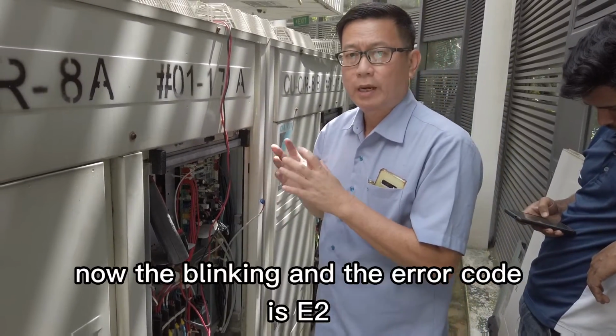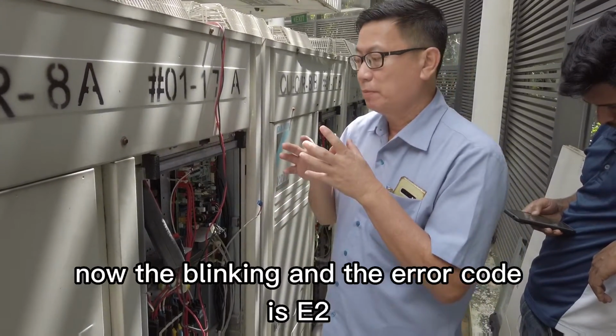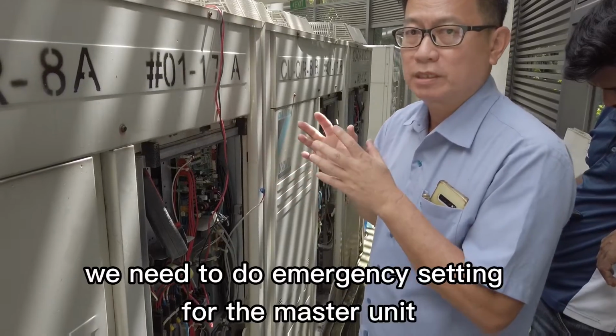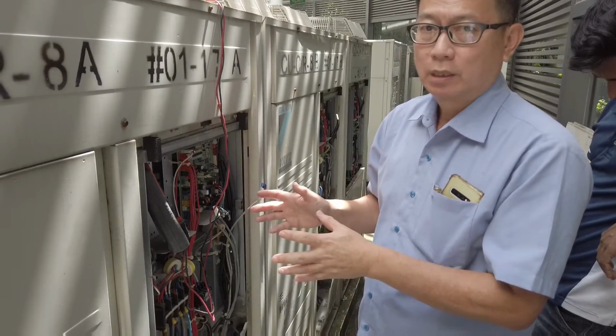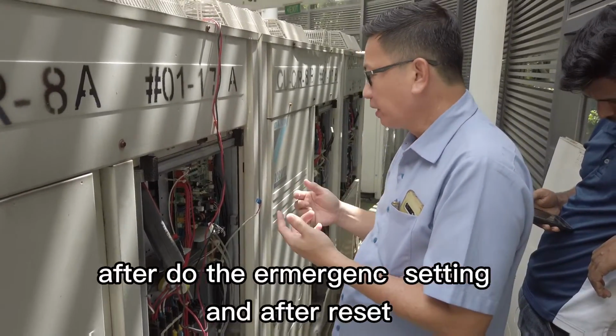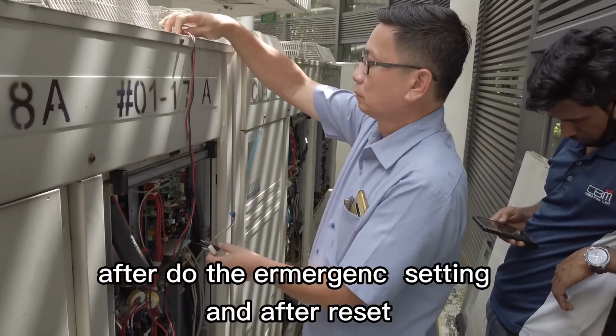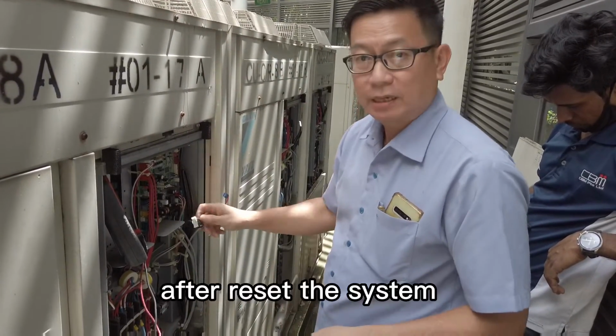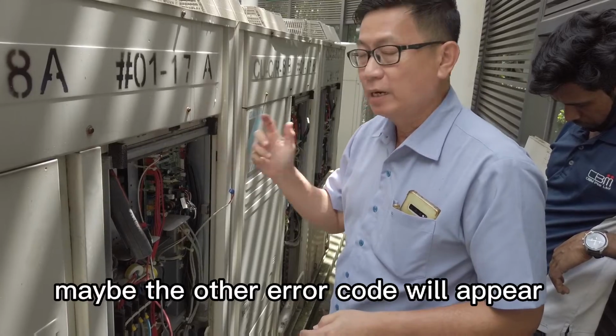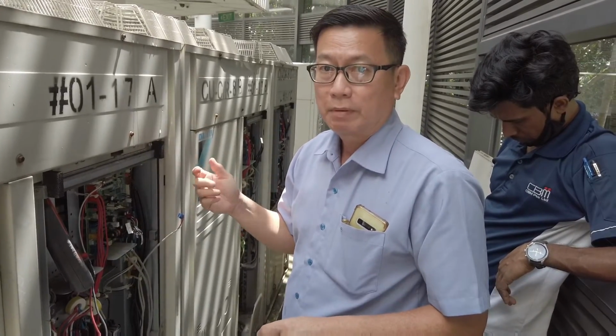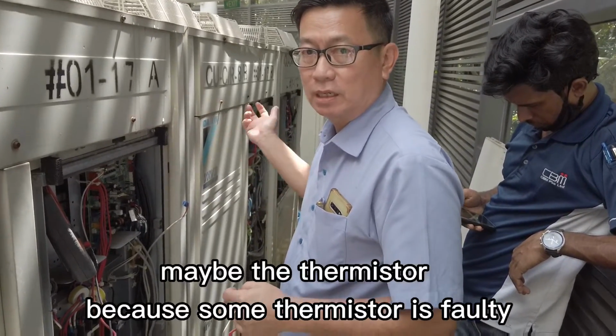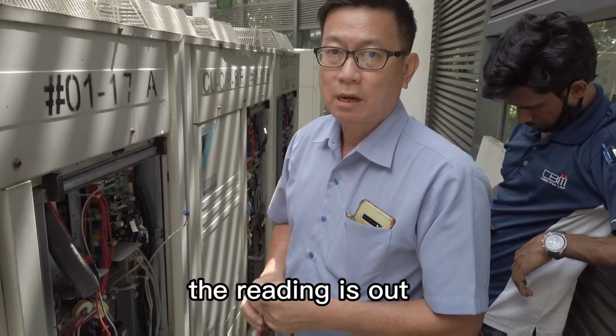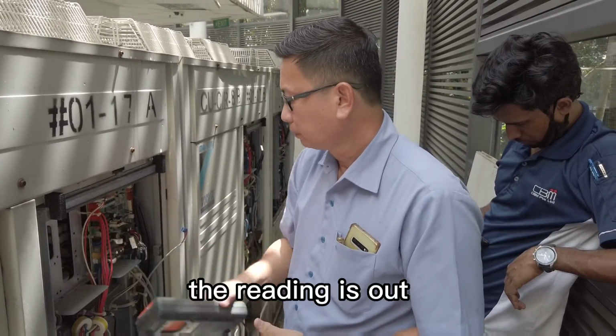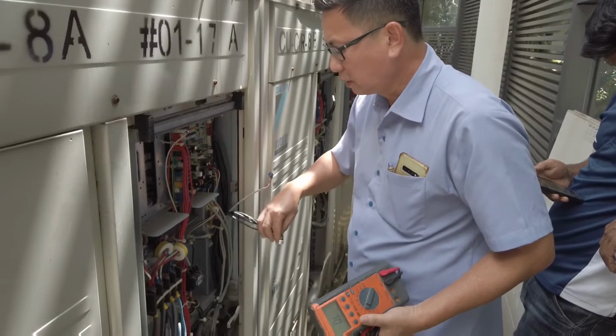Now the blinking, the error code is E2. Okay, after maintenance, we need to do emergency setting for the master unit. After you do the emergency setting and reset the system, maybe another error code will appear. Maybe the thermistor, because some thermistor readings are out. Okay.